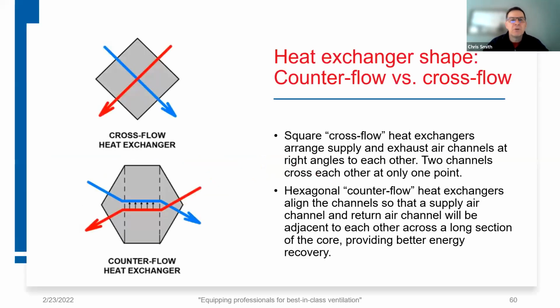What do we want to look for when we're doing best practices? First of all, the basic design of the device. We looked at those heat recovery cores or those heat exchanger cores. The shape and design of that core is a big factor. On the top there, you see the cross-flow heat exchanger. Basically, if you isolated two little air channels, a supply air channel and an exhaust air channel, those two would only cross each other at one point.